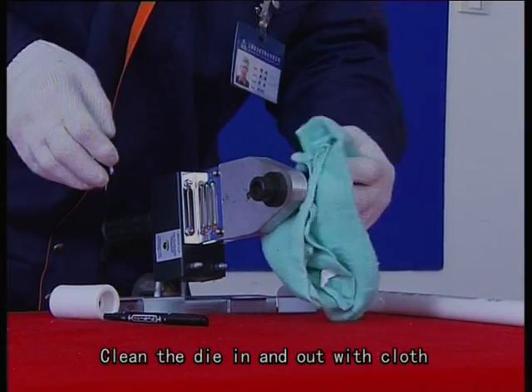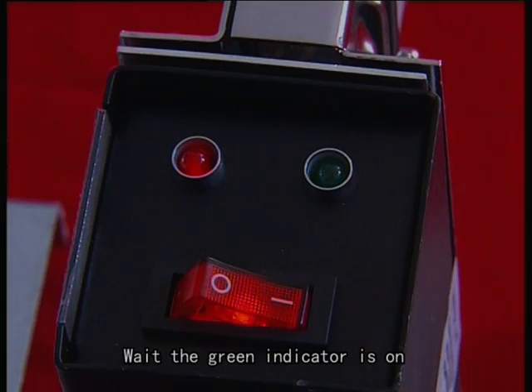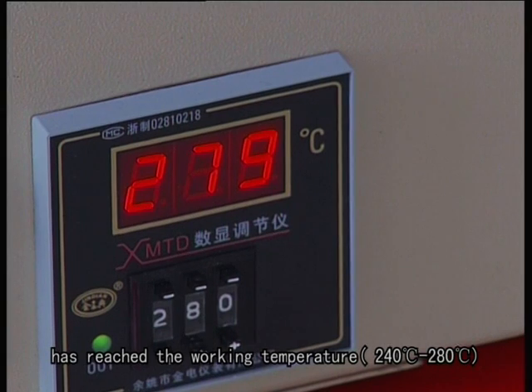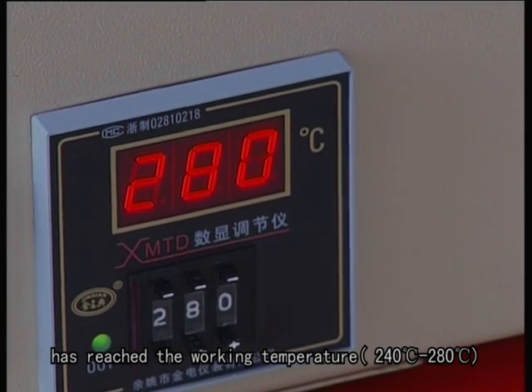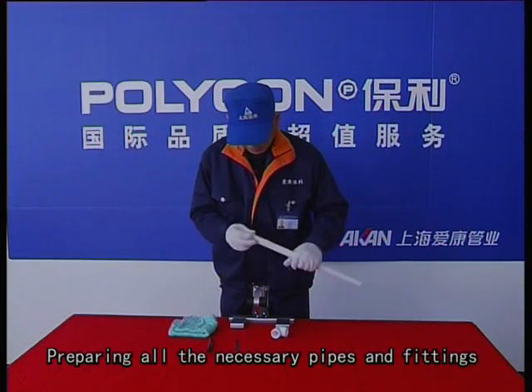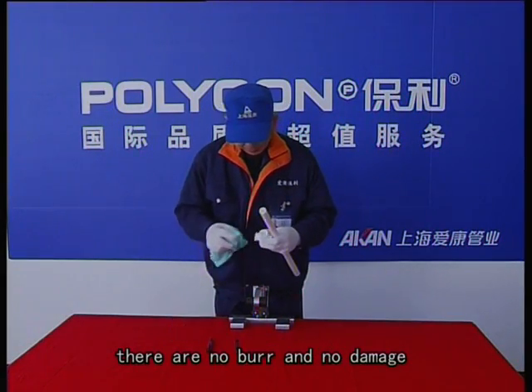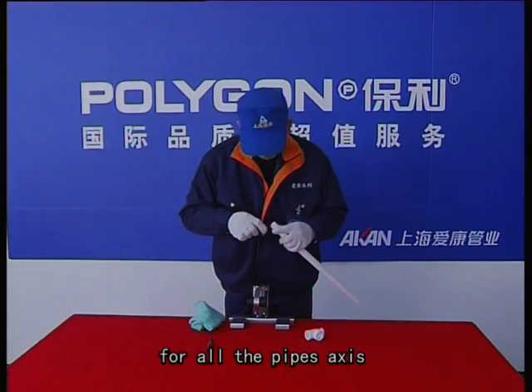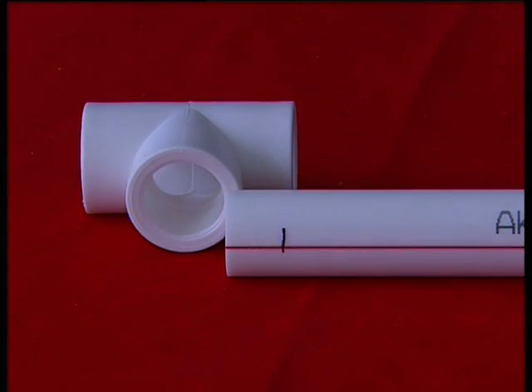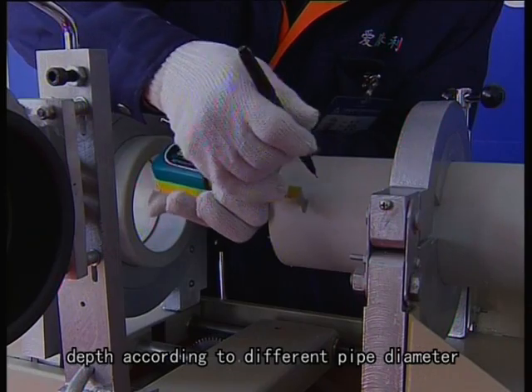Clean the die inside and out with cloth, then connect the welding machine power. When the green indicator is on, the welding machine has reached the working temperature of 240 to 280 degrees centigrade. Prepare all necessary pipes and fittings, and proceed with welding only after ensuring there are no burrs or damage. Clean the parts to be welded with a wiping cloth and mark the proper welding depth according to different pipe diameters.